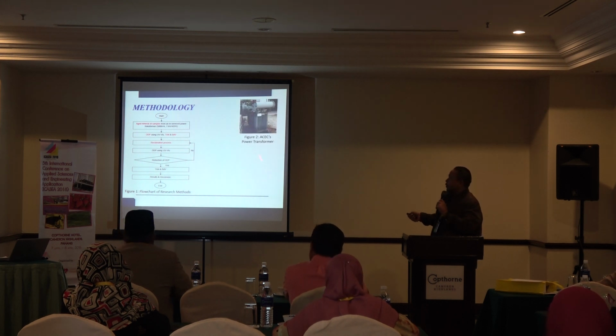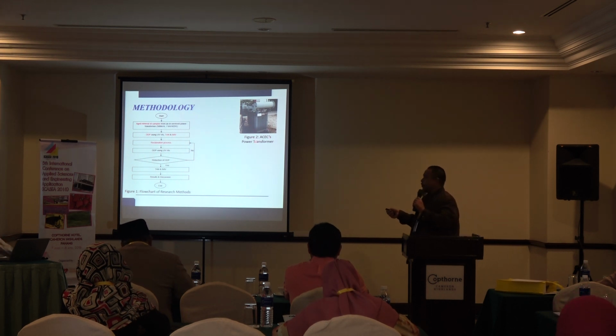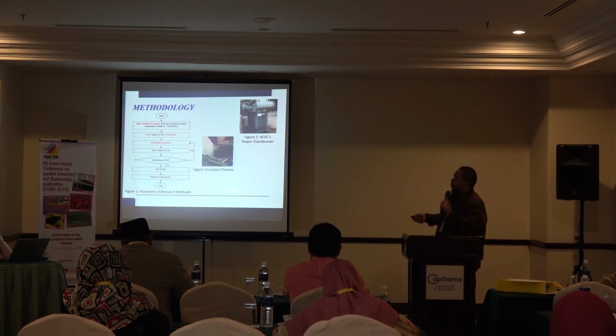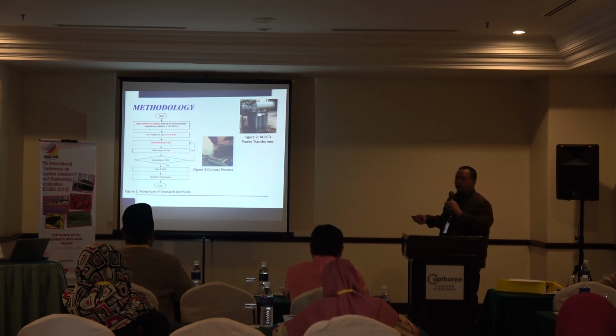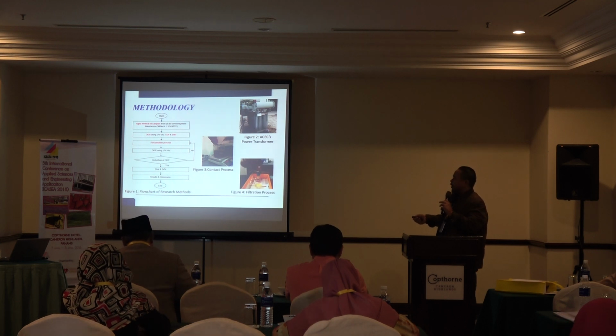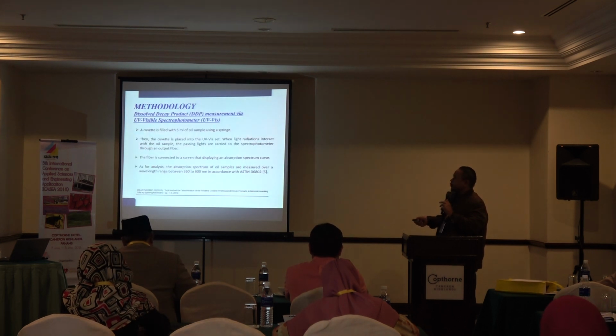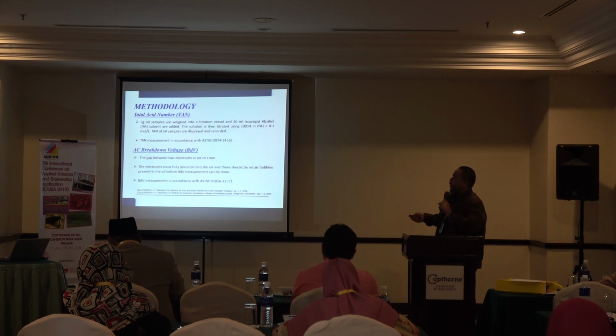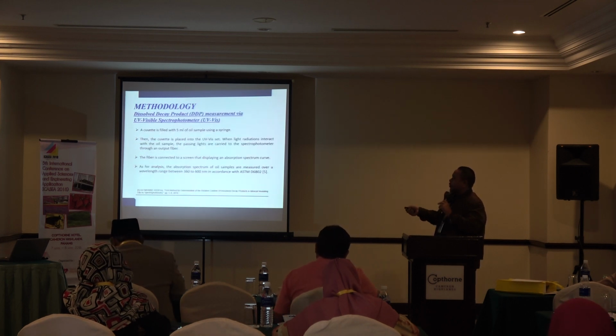So this is the transformer that we used. We took the oil samples from this in-service power transformer. Then we do the contact process, which means we do mechanical agitation by mixing the oil with the Fuller's earth. Next, we do the filtration process. Then, this is the method on how to measure. We are dealing with the UV-Vis.